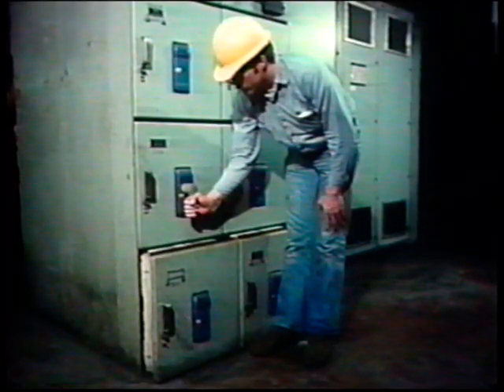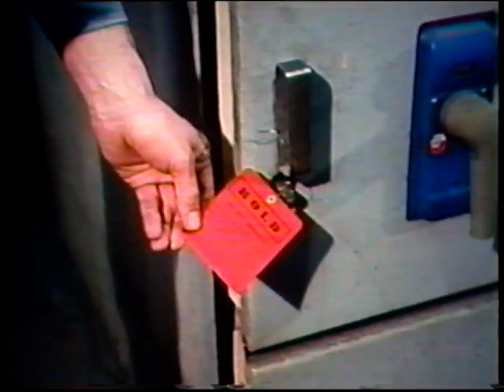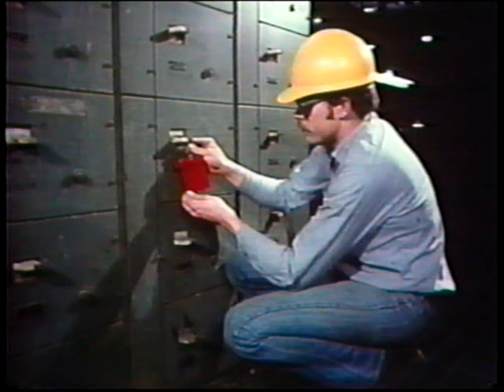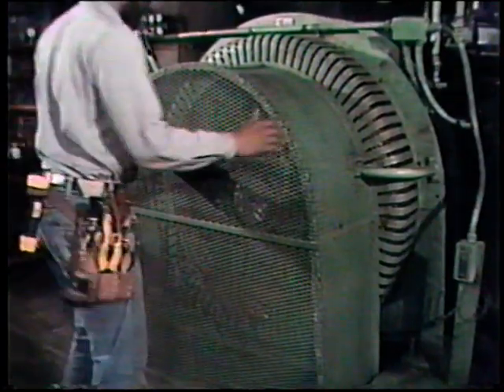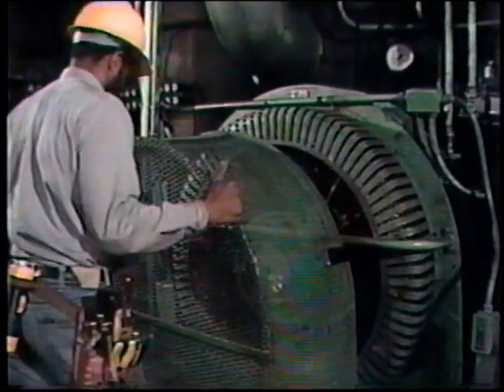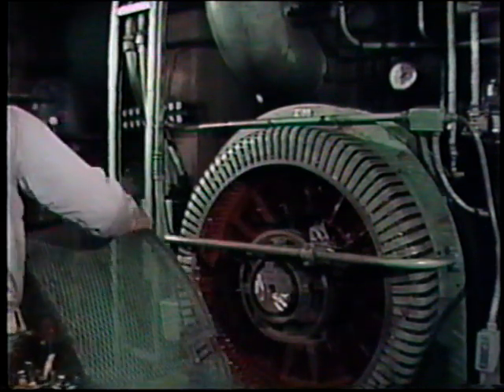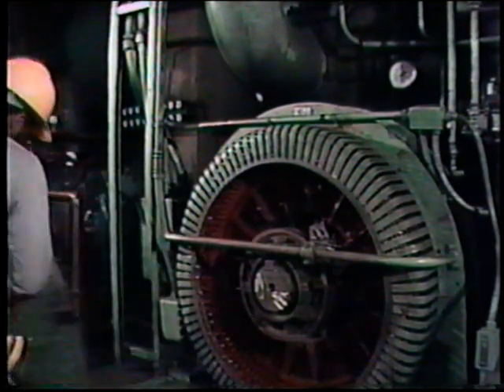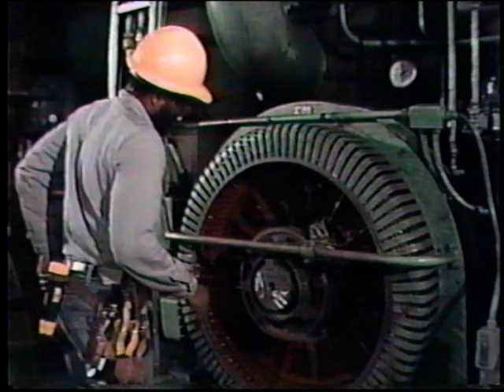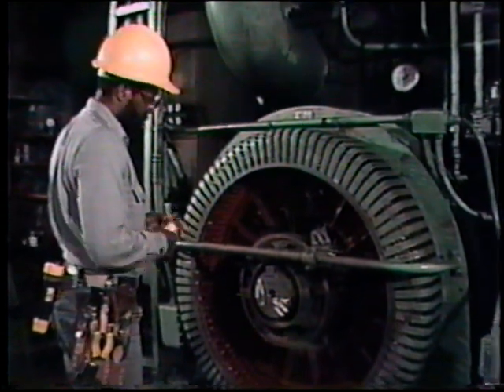Even when inspecting a motor that's not operating, you want to be sure to take all necessary safety precautions. First, have the motor de-energized and make sure the AC power supply breaker is tagged in the off position and the DC power supply breaker is also tagged out according to your plant's procedures. After both power supplies are tagged in the off position, remove the motor screen so that the motor parts are accessible. The screen is there for your protection when the motor is operating, so never remove it unless the motor is tagged out.